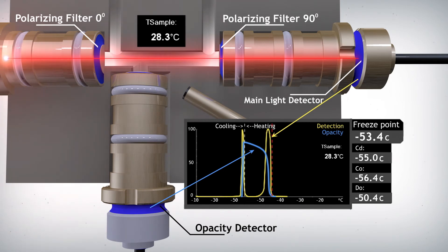Qualitative information can also be gleaned from the graph. Fine crystals always form and grow to larger crystals. The main detector is sensitive to these fine crystals, and the initial fine crystal formation is denoted in the results as CD, for crystal detection.